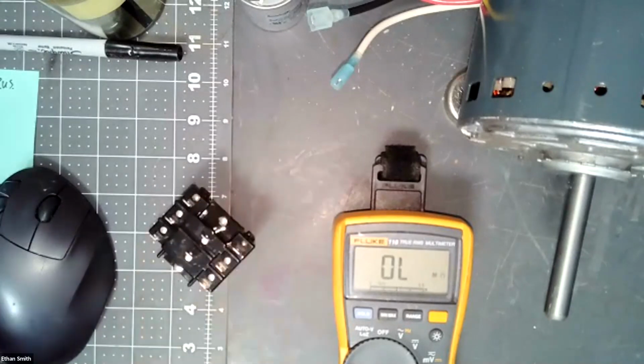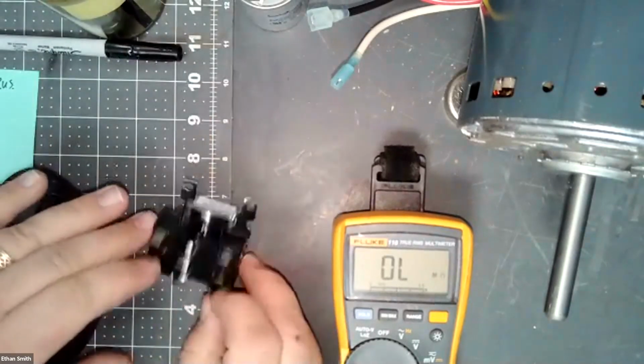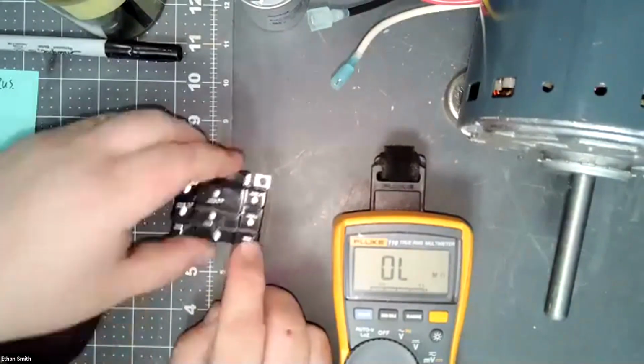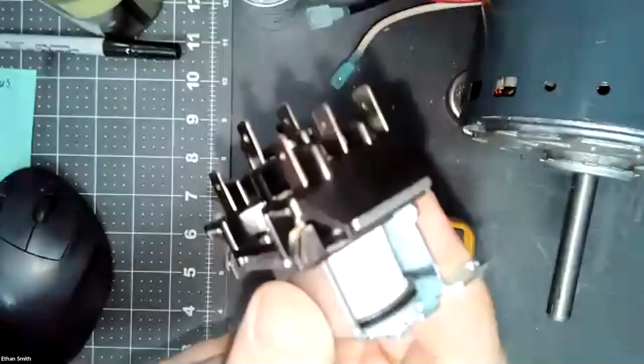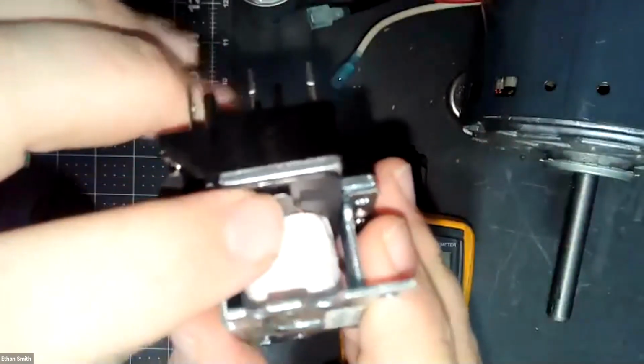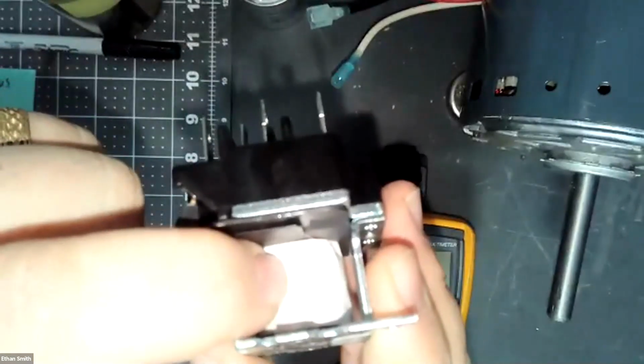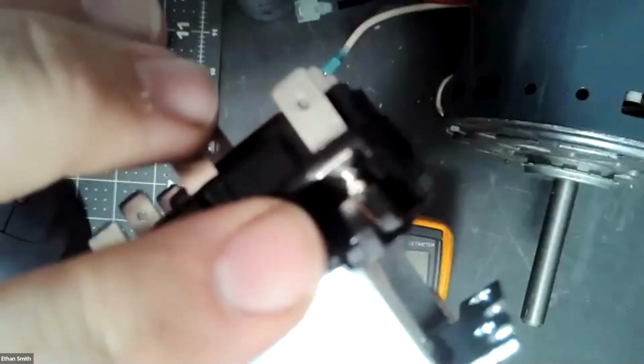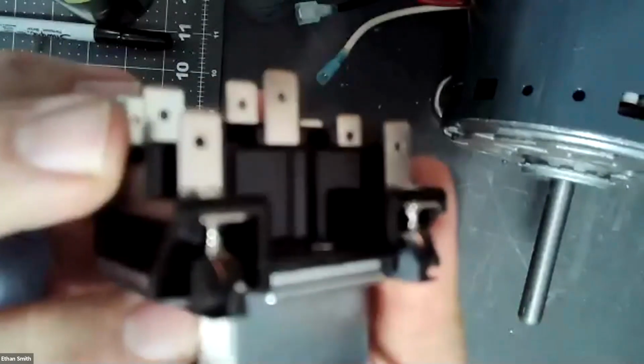So coils, when they're energized, we mentioned that my coil contacts are down here. And if we look at this really closely, you can kind of see right down this wire, you'll see a little wire track that comes down to this solenoid pack that's down here. Turn this light off, see if we can see it any better. But you can see where this post is. There's a little wire inside there, and that tracks around down into the pack. Again, we've got another wire on this side that tracks down into this pack. And this is just a big coil of wire around an iron core that is operating these switches.